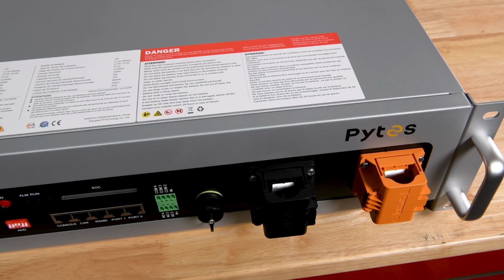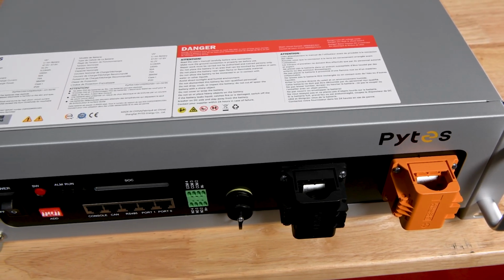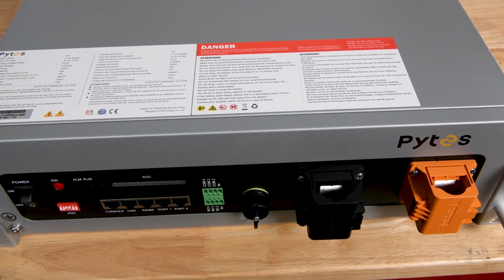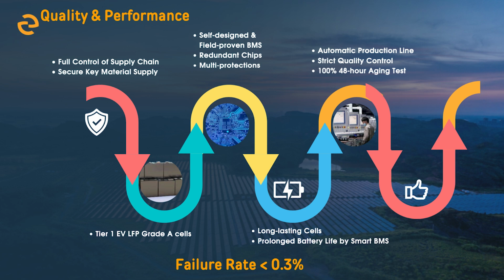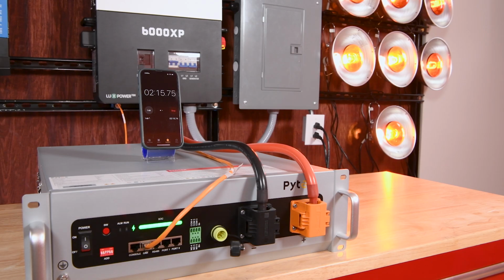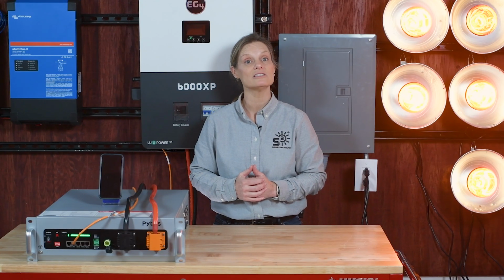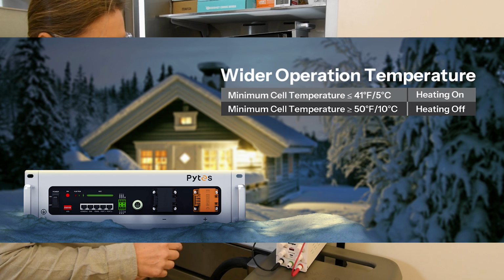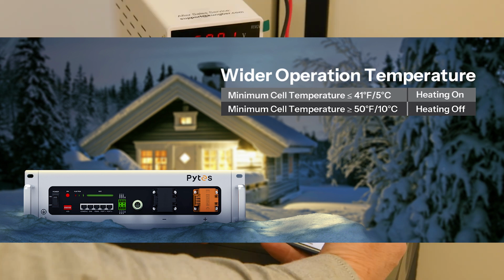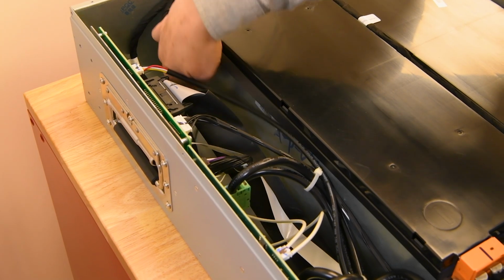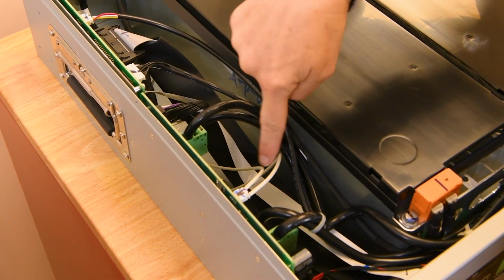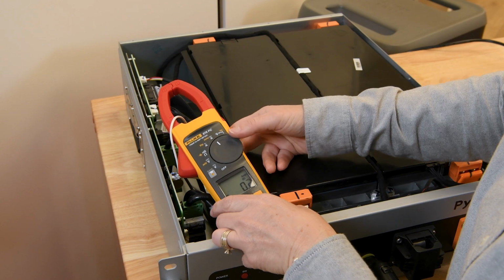Safety and reliability are at the forefront of Pytes design. The V5 is UL 1973 and UL 9540 listed, meaning it has passed rigorous third-party safety testing. Its integrated BMS ensures safe operation, protecting against overcharging, over-discharging, and temperature extremes. During our discharge test, the V5 safety features engaged as expected, showing alarms and limiting discharge when the battery reached critical load levels. The integrated heaters also performed well, activating automatically to maintain optimal battery temperature during charging in colder conditions. Unlike some other systems, the V5's heating elements are smart controlled, ensuring efficiency and only engaging when necessary.